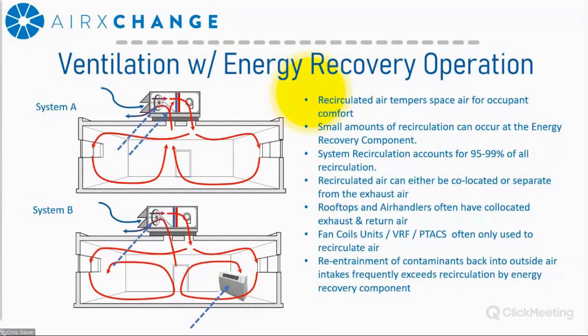You also have to be aware of any reentrainment. Reentrainment is when exhausted air inadvertently enters back into the space air through the outside air intake. Now, there is a small amount of recirculation that happens at the energy recovery component. But when you take that percentage into account with the entire system flow and the system recirculated air, it's usually magnitudes below what reentrainment or recirculated air is in terms of returning space air back into space air.